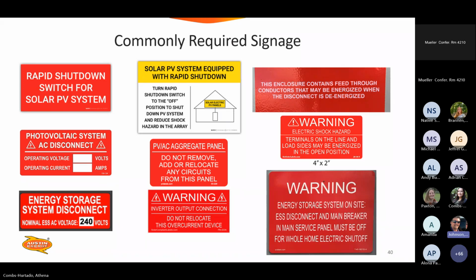Okay, commonly required signage: rapid shutdown switch for solar PV system, photovoltaic system AC. This part does need to actually be filled out. Your operating voltage, those solar modules, they add up. They can become very high voltage very fast on these dwelling units. And then also operating current. There should be an operating current filled out in that blank too. Energy storage system disconnect. We do need the actual system voltage written on that.